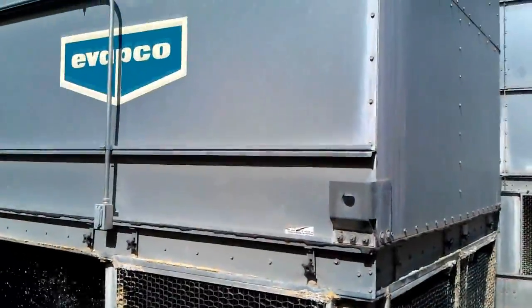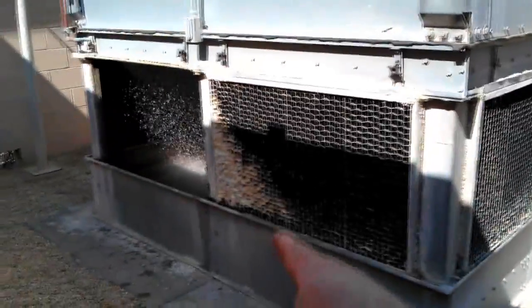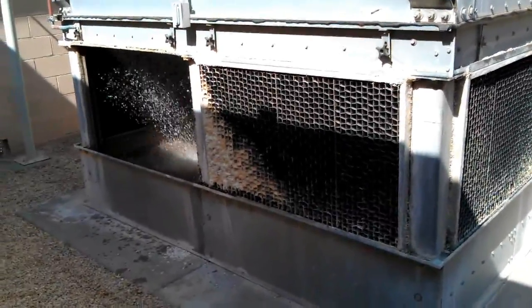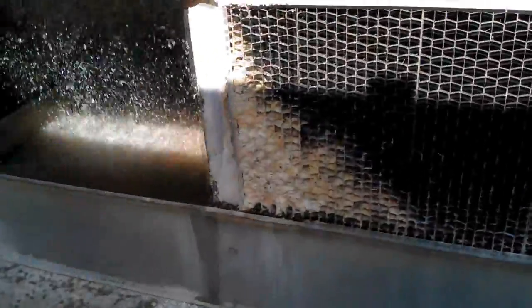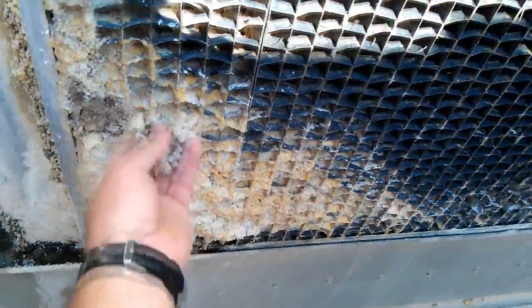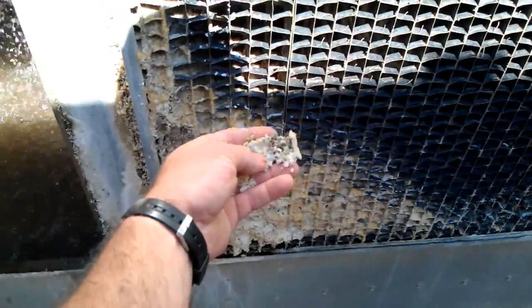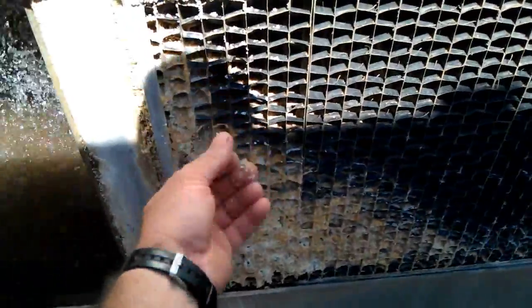What is up? Got an Evapco cooling tower that likes to get some buildup of sediment right there. That's probably due to where the flow of the air is the slowest. The chemicals are likely still doing their job because that's soft — that's all the chemical stuff does, is keep the material soft. Then you need to rely on the speed of the moving water to keep the minerals and stuff suspended in the water so it won't build up on piping and things like that.